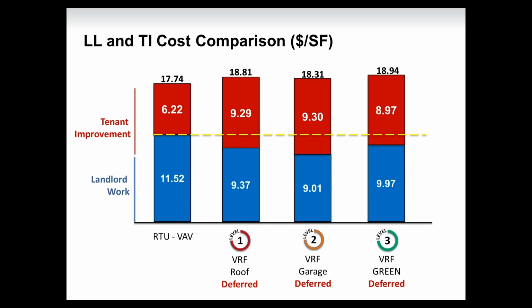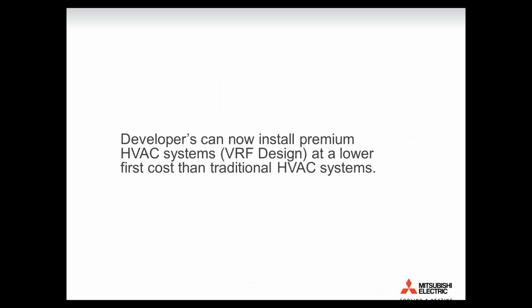We consider how we satisfy a first cost-driven customer along with some very aggressive ways to minimize his costs by shifting them to the TI portion of the project. And we accomplish this by providing only 128 tons of outdoor units connected to the indoor units. This 128 tons of cooling would temper the building to maintain it at 60 degrees in the winter and 80 degrees in the summer until such time as tenant leases are secured. If anyone is interested in further discussion on that, we'd be happy to talk to you about that at a later date. So with that, bottom line is developers can now install premium HVAC systems of VRF design at a lower first cost than traditional HVAC systems.